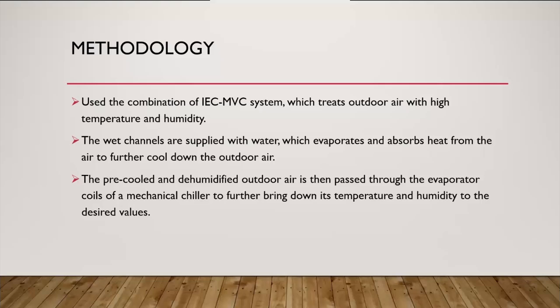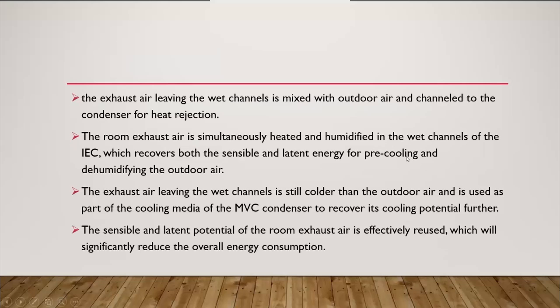dehumidified outdoor air is then passed through the evaporator coil of the mechanical chiller to further bring down its temperature and humidity to the desired values. The exhaust air leaving the wet channel is mixed with outdoor air and channeled to the condenser for the heat rejection. The room exhaust air is simultaneously heated and humidified in the wet channel of the indirect evaporative cooling, which recovers both the sensible and latent energy for pre-cooling and dehumidifying the outdoor air.